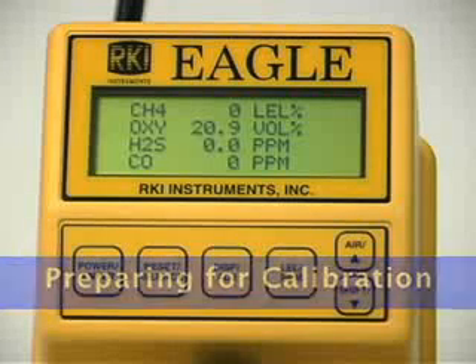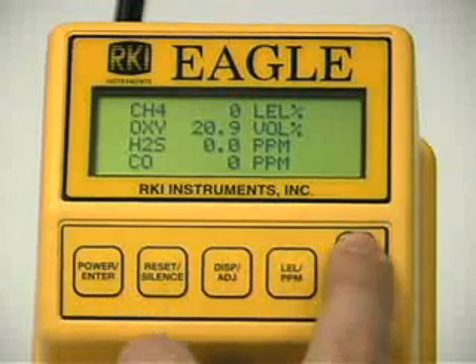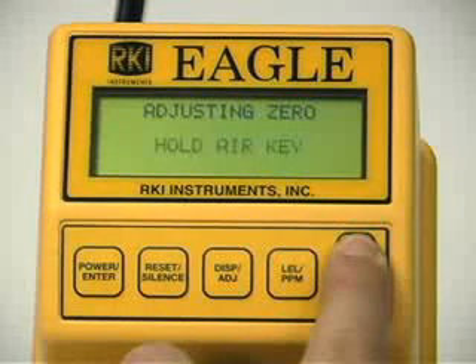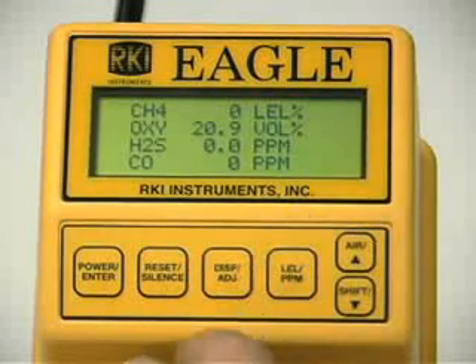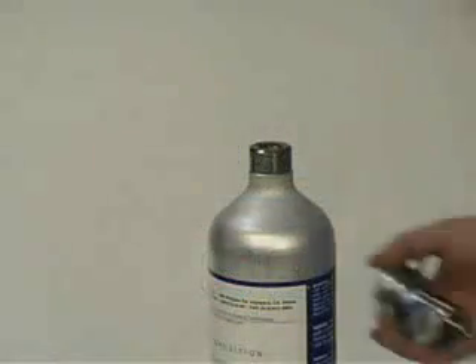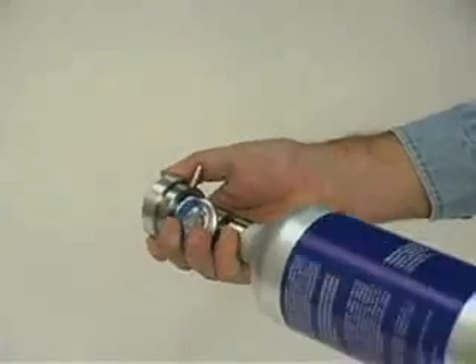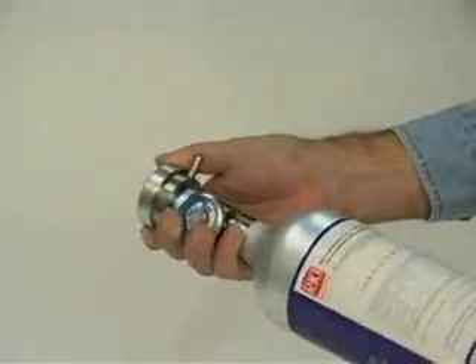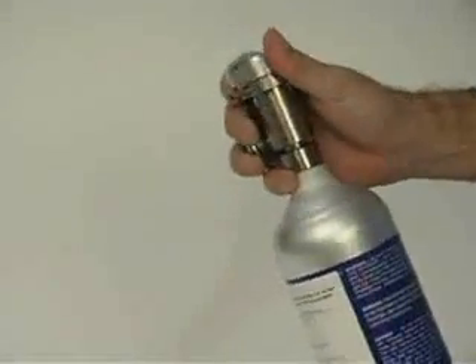Take the EAGLE to a non-hazardous location with fresh air conditions. Turn on the EAGLE and allow one minute for warm-up. Perform a demand zero by pressing and holding the air button until the display instructs you to release the air key. This automatically sets the combustible gas and toxic circuits to zero and the oxygen circuit to 20.9%. Screw the calibration cylinder to the regulator, then connect the tubing to the regulator.